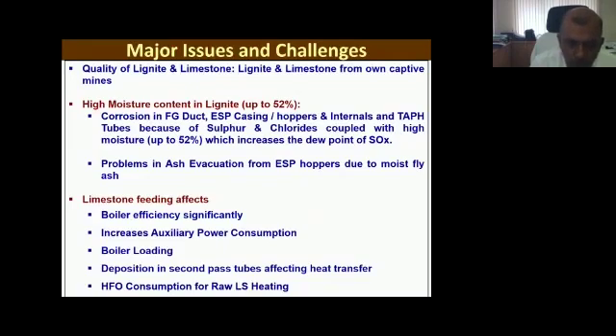Apart from this, for compliance with the new environmental norms, we have to dose limestone at around 7 to 10% of the fuel, which is almost 125 to 140 tons; earlier it used to be 100 tons per hour. This consumption of limestone with lignite lowers the boiler efficiency by almost 1%. If you fire almost 10 TPH of limestone per hour, it reduces boiler efficiency by around 1%.